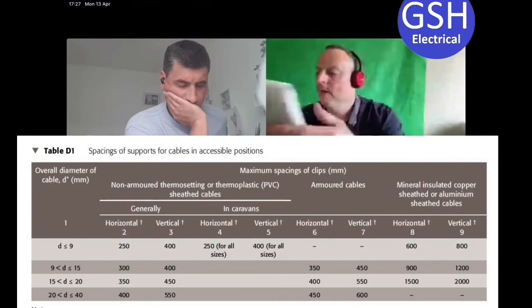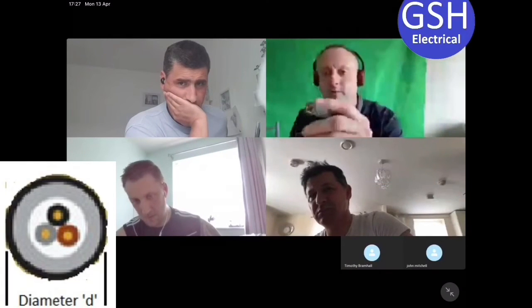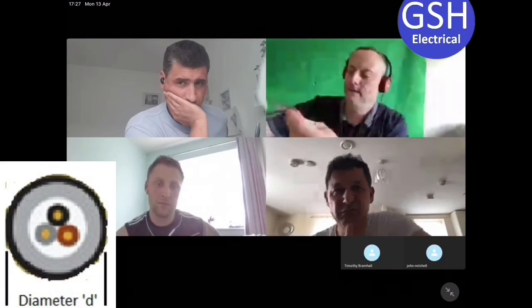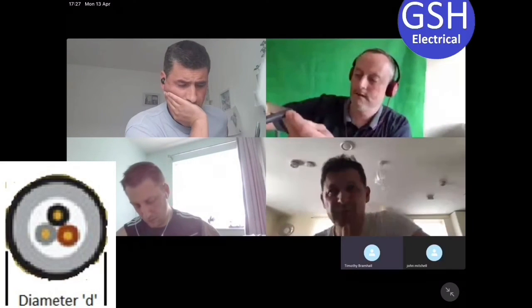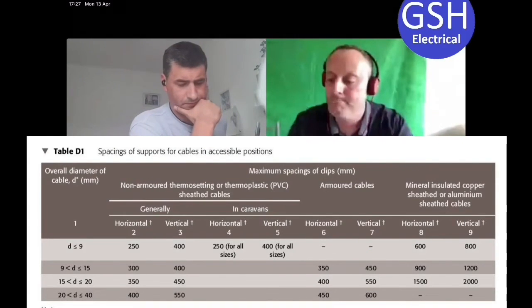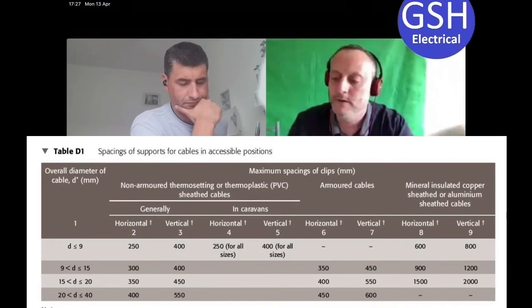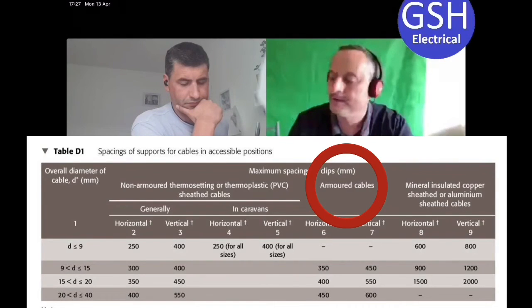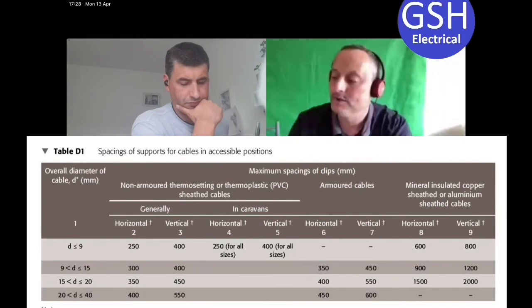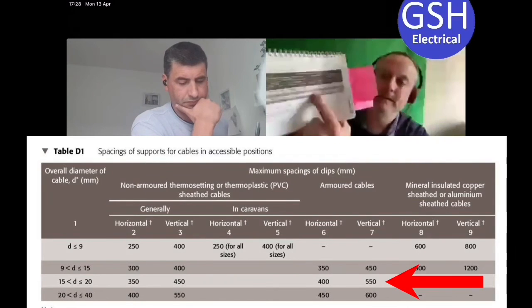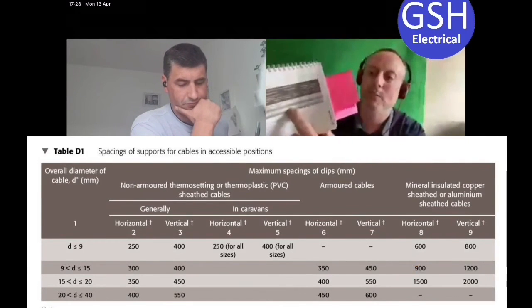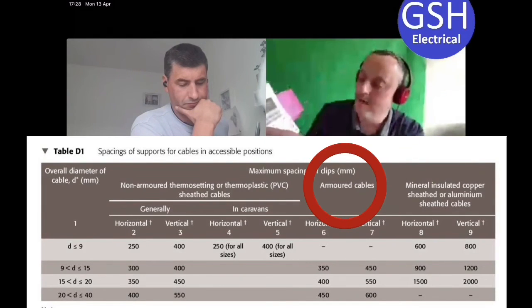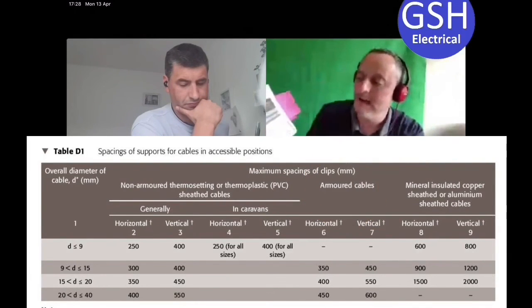Let's do an armored cable. Measuring its major axis - 16mm diameter. Back to column one: row one is up to nine, row two is up to 15, so now we've fallen to row three which is greater than 15 and up to and including 20mm. For armored cable we move across to columns six and seven - steel wire armored is 400mm horizontal and 550mm vertical. Compare that to the twin cable columns - the numbers are actually greater, so the armored cable is more rigid and the maximum distances are larger.